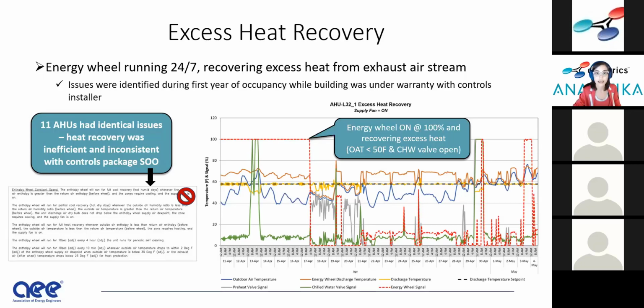I hope everybody can hear me. It can be used for continuous commissioning and onboarding commissioning for a new building. And before you think, oh, it's a new building, I'm not going to find much, I wish my colleague were here, who has worked with a lot of new buildings. He could tell you just how many faults he finds in brand new buildings, how we can support people to get it fixed under warranty. If you don't do this, you can have unintended energy use. Your whole system is set up for this heat recovery. So you can have chilled water valves that are starved. You can see, 10 degrees above set point is what we're overheating here.